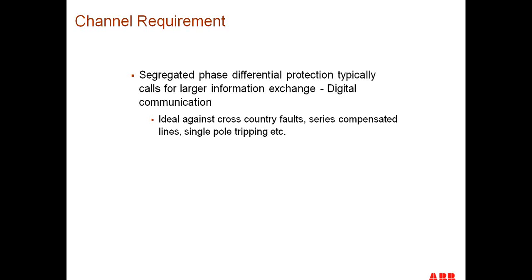That works very well, and it minimizes the data requirements you need, and the channel could be set to be less than 4 kilohertz if you use that approach. But you lose some phase segregation to do that. You don't get phase identity about which phase the fault is on. But if you're doing 3-phase tripping, that's fine. On modern relays and modern communications techniques where you have 64 kilobit channels or so, it's very easy to send enough information that we can use segregated phase differential instead of combined sequence differential.